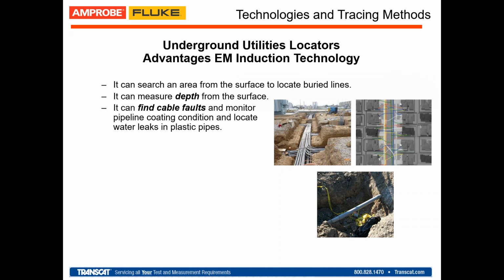Locators can also find faults. Underground utility locators come with special accessories called A-frames that allow users to detect the segments or areas of the cable that present faults—we'll talk more about that in the product details. They can also pinpoint the position of joints, which is less of an electrical safety benefit and more for utilities in general, such as pinpointing joints in metallic water or gas pipes.